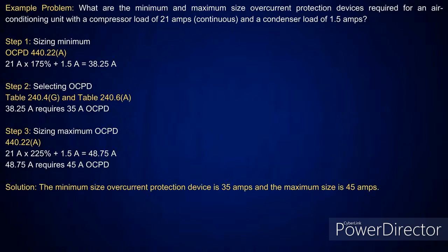Okay. Now here's an AC unit. I've got a compressor load of 21 amps and a condenser of 1.5. Same principles apply here. When I look at this, I'm going to look over at 440.22. Now, some of y'all that have your 2023, because we're doing this on 2020, but I do like to tie in the 2023 if there's a change that's made. And when you go over and look at 440.22A, they sort of did it like they had it in the last cycle. I expect this eventually to be 440.22A, A, B, and C. But right now they have them as exceptions like it used to be in 430.52C1.